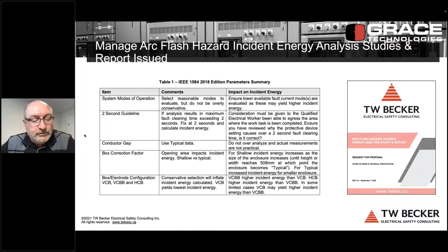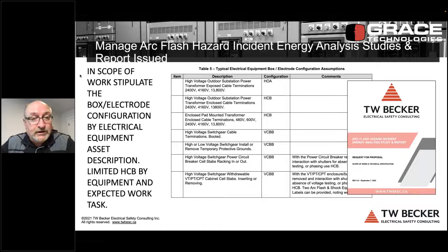It's completely wrong. So again, within your electrical scope of work for these studies, you need to take control of parameter selection. You stipulate the parameter selection, and the consultant then validates why they would agree or disagree with you. On the box electrode configuration selection, you again take control, and the consultant has to advise you why they would select a very conservative HCB, horizontal conductor box, electrode configuration. Ultimately, you tell them what the electrode configuration is, and then they justify why they would select a different one. This scope of work and technical spec is part of your electrical safety program, your document system. So again, some guidance there.